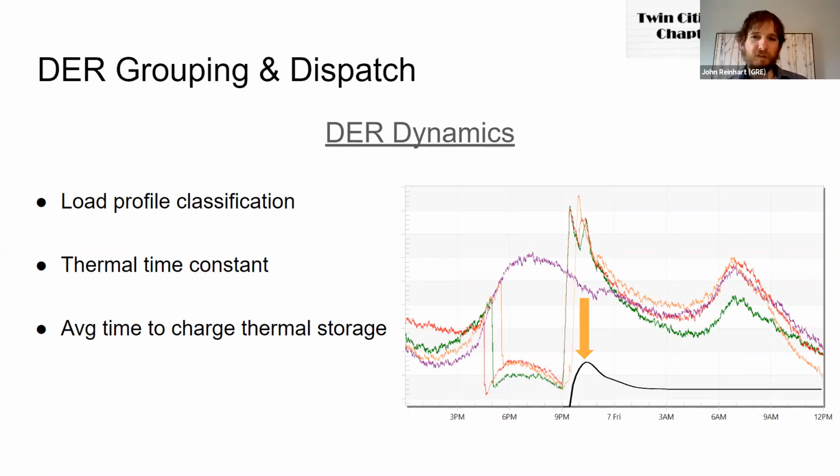And I'm showing several different days overlaid over a 24-hour period. The point of this graph is to show that when load is curtailed, and some of this load was curtailed due to water heaters or air conditioning systems, when that load comes back on, it may actually bring back on more energy than in that instant that it's recharged.